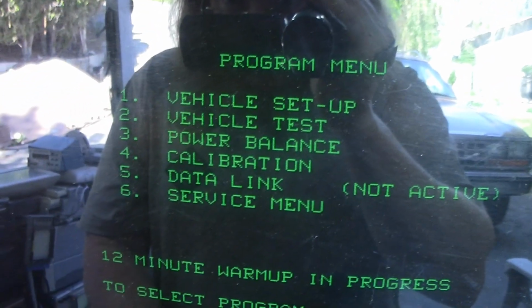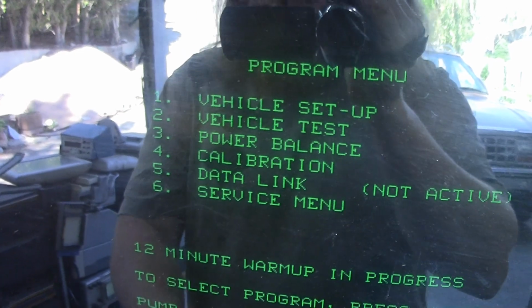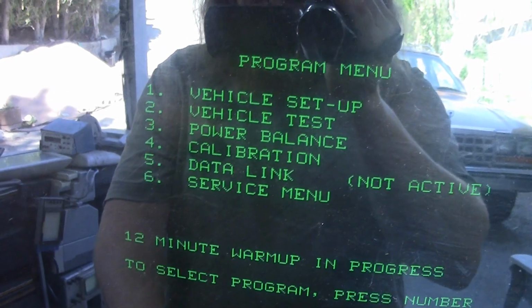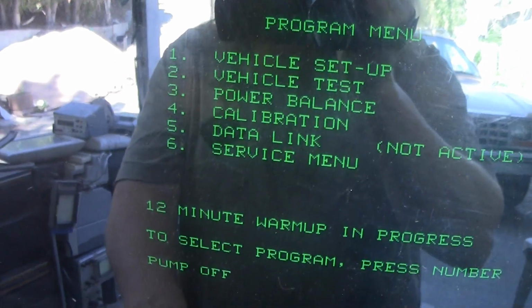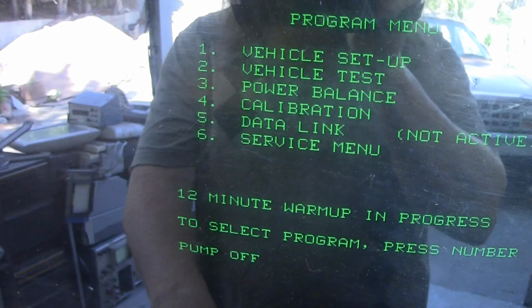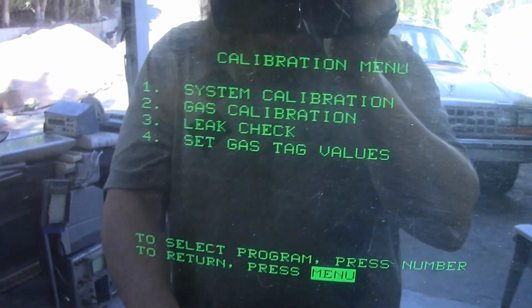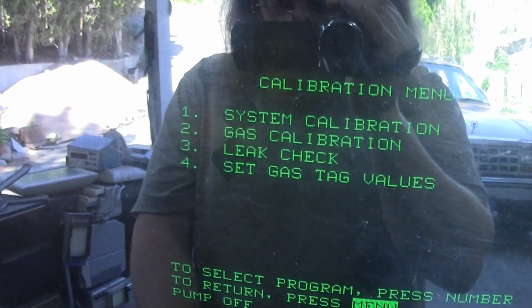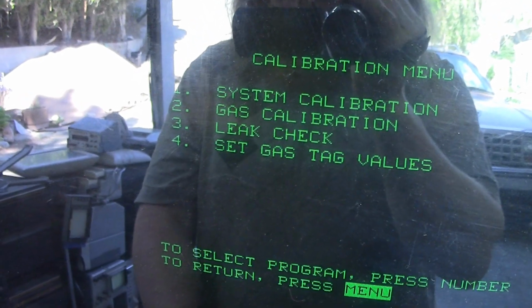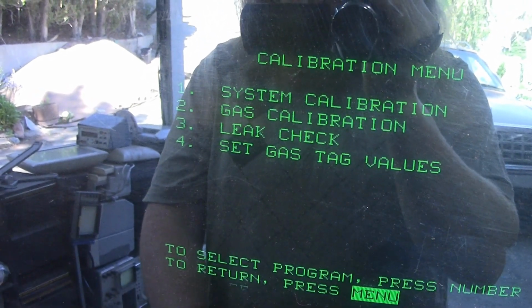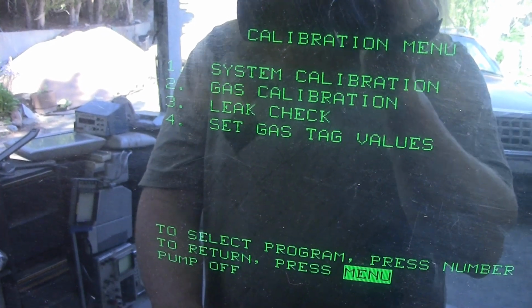So I'm just going to go back to the menu again. Power balance test. That's another test that requires the engine to be attached and running, so we can't do anything there. Our calibration, that there is for calibrating the system, so it goes back to that initial calibration. Gas calibration, leak check, and set gas tag values. The gas tag value is something that you will find on the back of your gas analyzer.